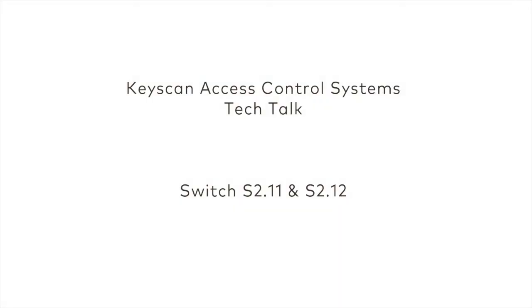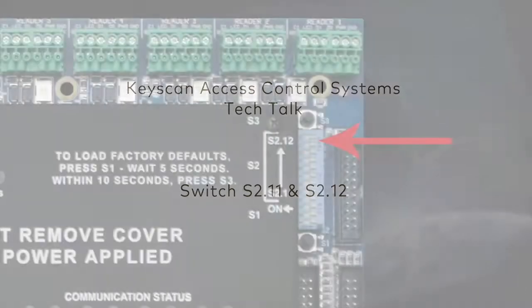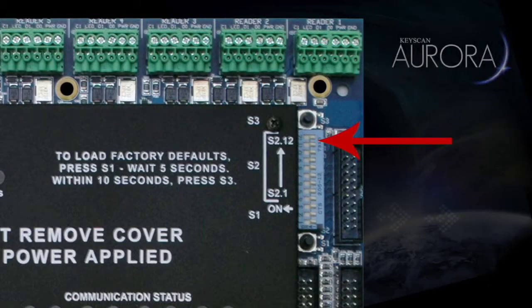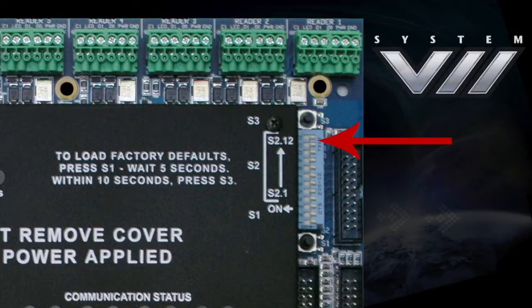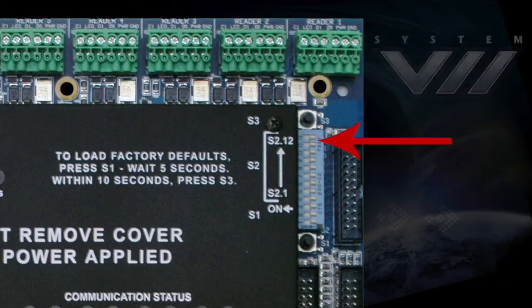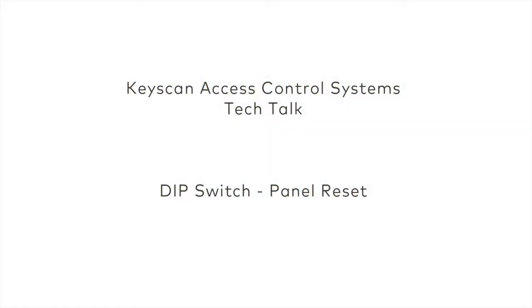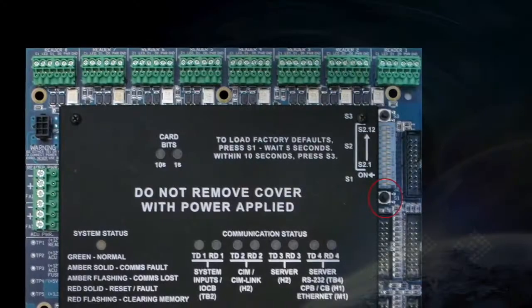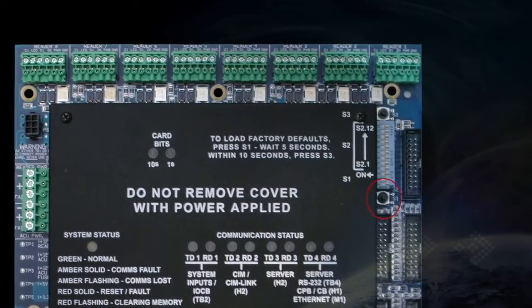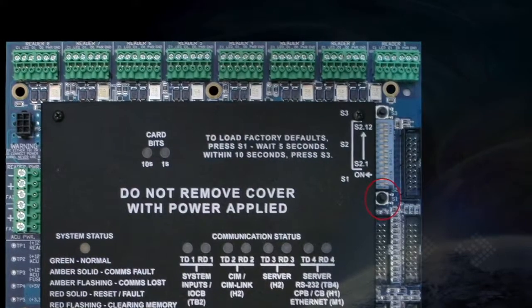Switch 11 and 12 are used for software selection. The default setting is set to Aurora software. If you are installing an access control unit to be used with either System 7 or Vantage software, you must set these switches accordingly. Any time that the DIP switch settings are changed, a reset must be performed so the unit recognizes your new settings.